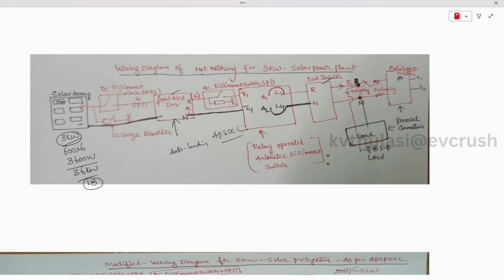For example, here we are generating more, so if you have a load, that will absorb the load and remaining will be exported to the solar meter. So this is how we have to connect our solar plant in parallel to the existing load. Here our solar meter, or the grid, will act as a parallel connection, and the load also will act as a parallel connection.